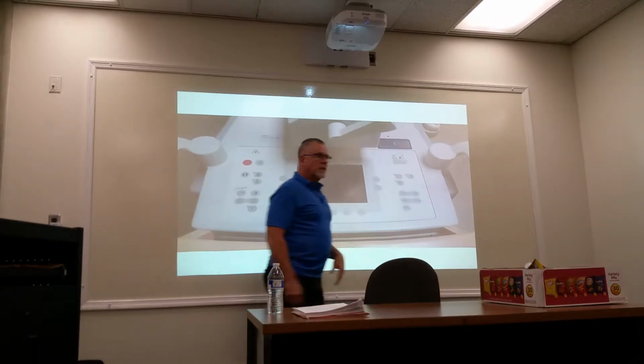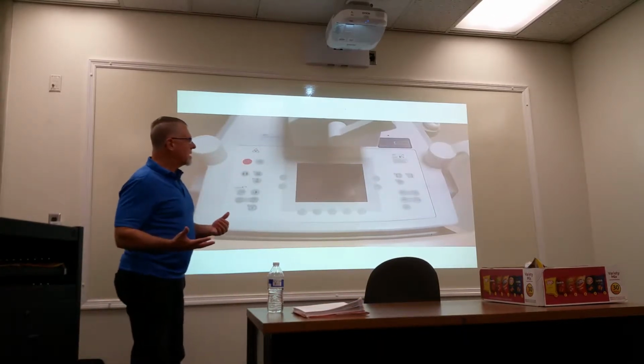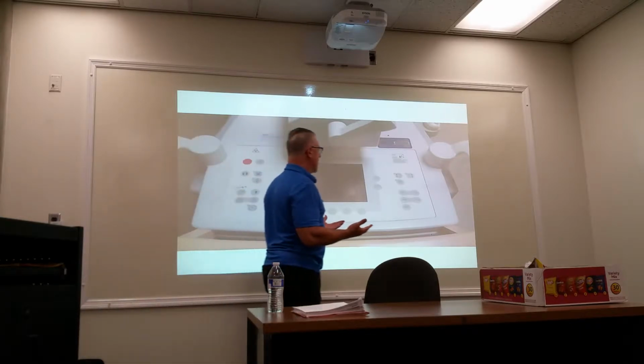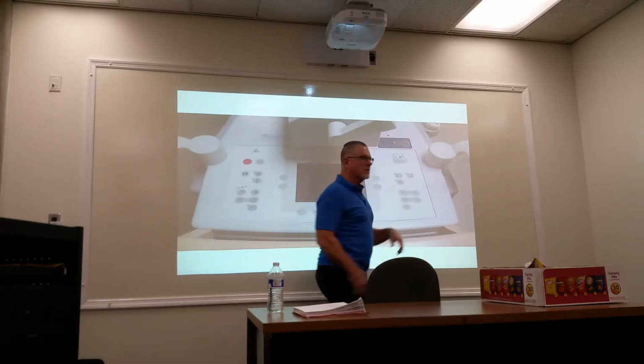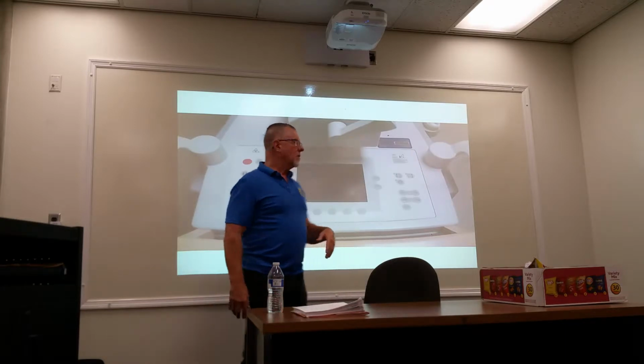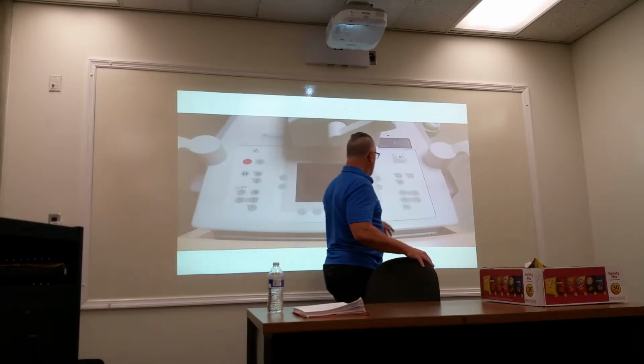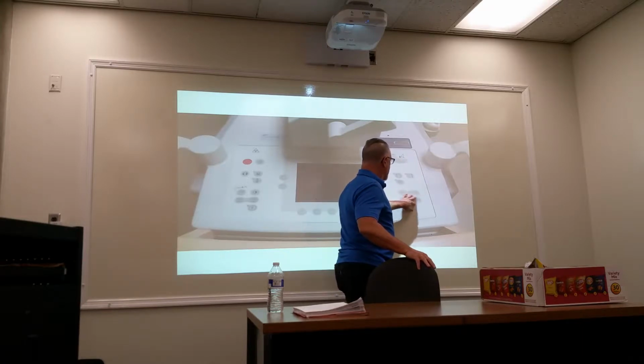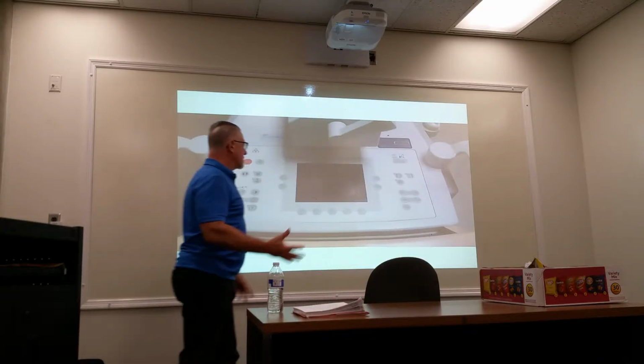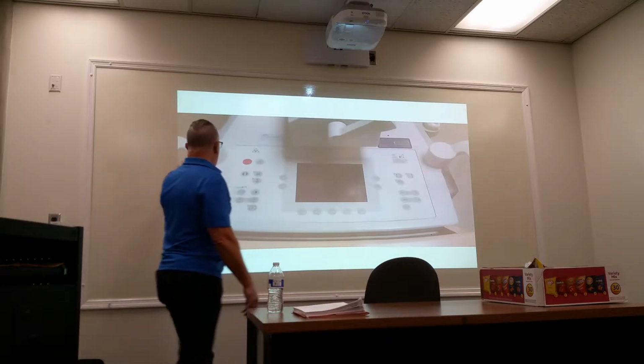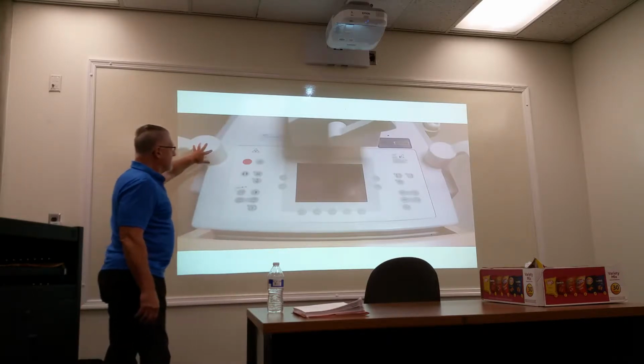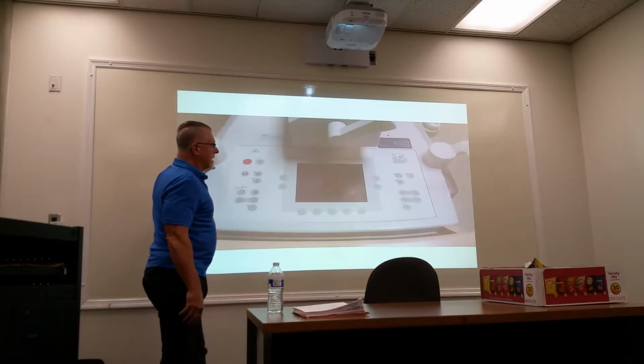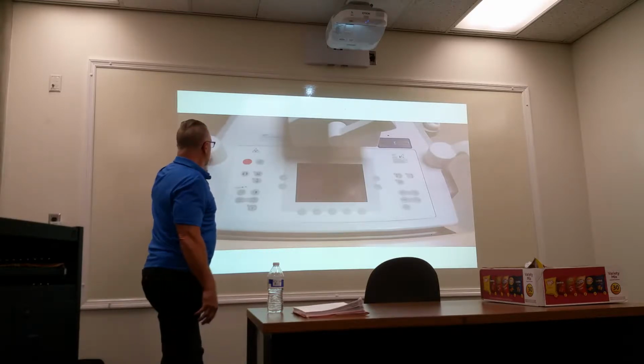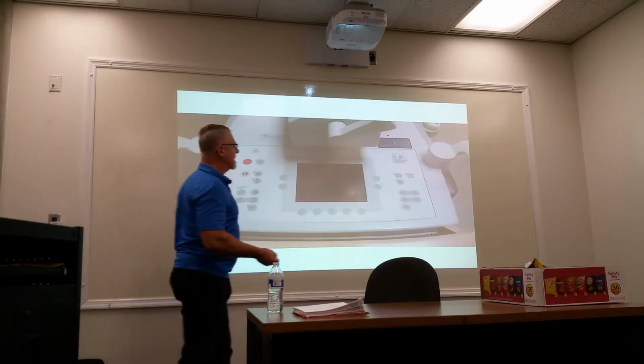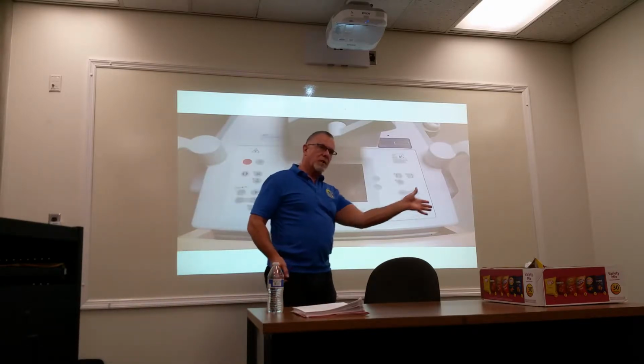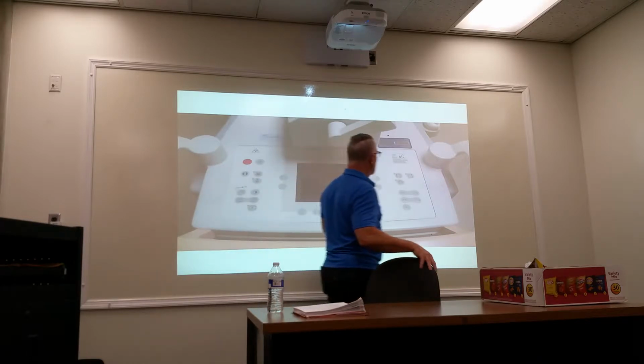Collimation in mobiles, there's usually two of them. You have the blade type, so you can have rectangular fields of view, but there's also usually an aperture control. So that gives the doctor a lot of leeway. And then, of course, you've got your positioning controls for turning, extension, and things like that. For this particular unit, these drive the direction of the wheels. You notice there's two of them, so the wheels are independent, which is kind of fun. Especially if you have one wheel going this way and one going that way, it doesn't go very far.